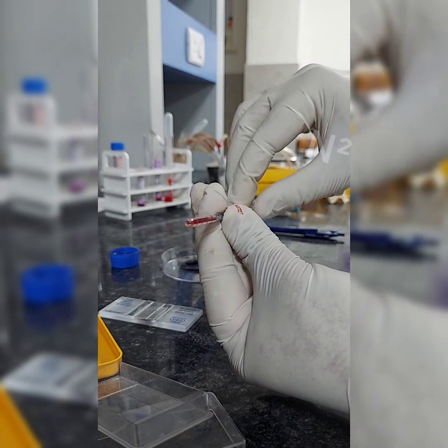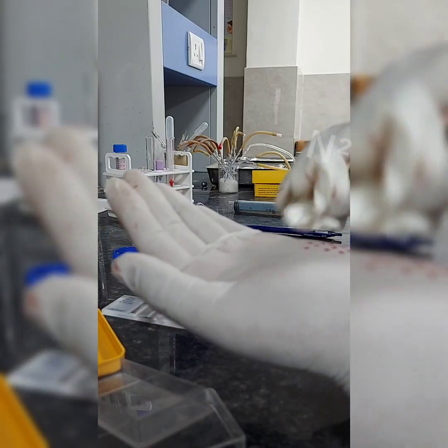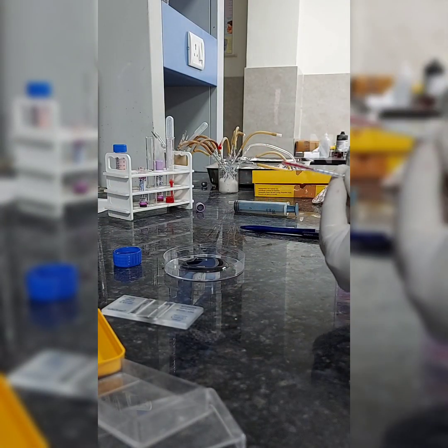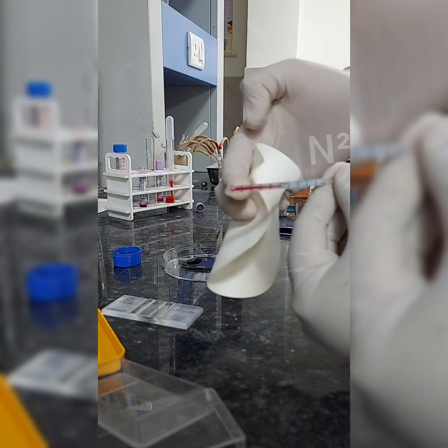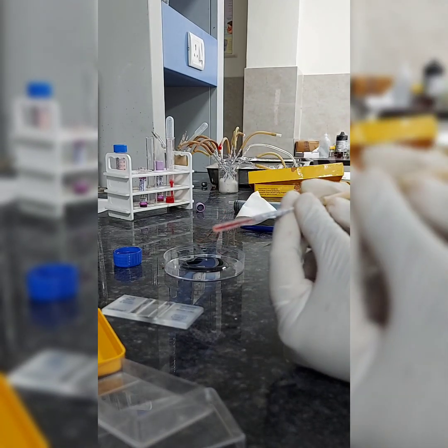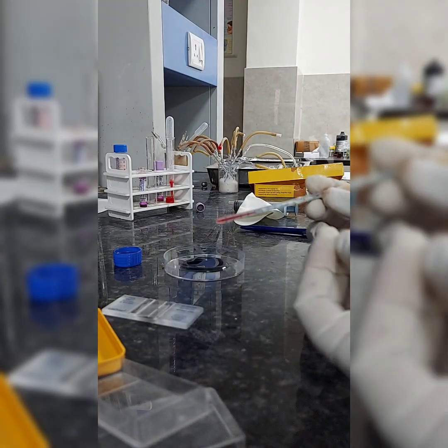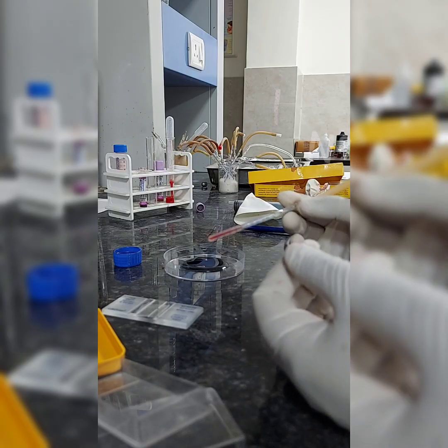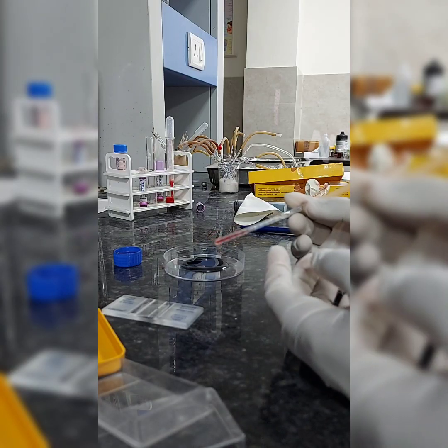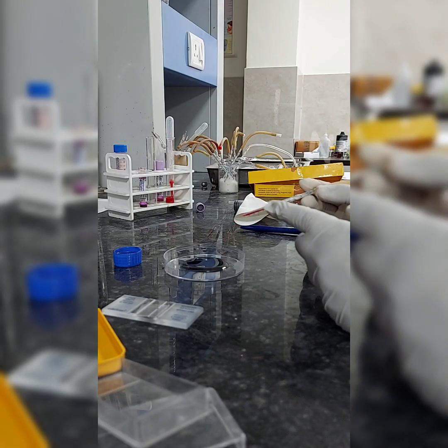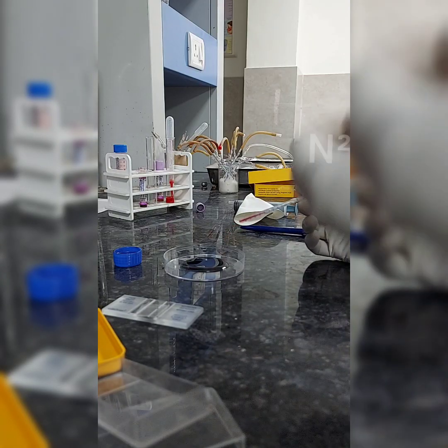Now I will keep it there only. Okay, try to clean my palm. Then I will complete and make sure you have completely cleaned the edges. Make sure you don't tap it on a filter paper or cotton, because those materials will draw the fluid out from the pipette. So clean it, if possible, with a cloth or a soft material. Then clean the sides of the pipette, because there is some amount of blood sticking to the glass capillary end, so that might give you a higher result.